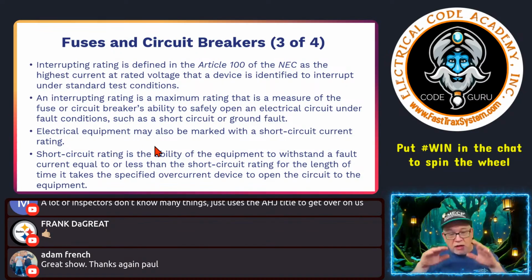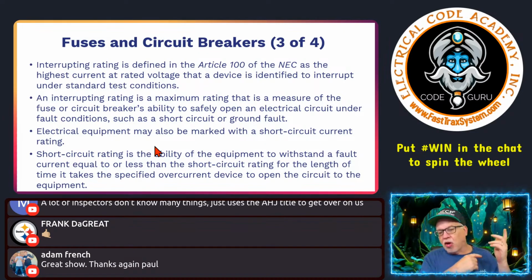So usually this is done by the manufacturers. You'll get a breaker with an AIC rating, and then you'll get a short circuit rating for the equipment. Let's say it's 22,000 SCCR, and then the breaker will be 22,000 at least, interrupting rating. And again, everything works happy. And then all you have to do is make sure that you know what your available fault current is from the utility down. And usually they may give it to you at the secondary of the transformer.